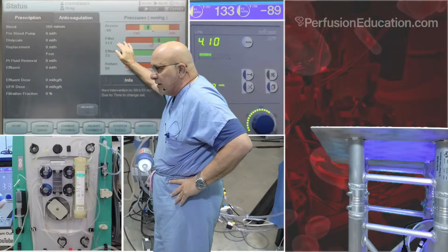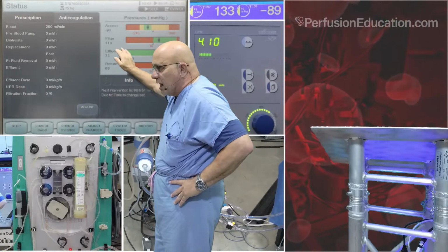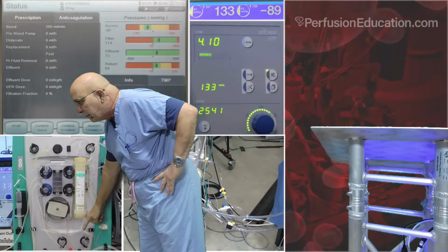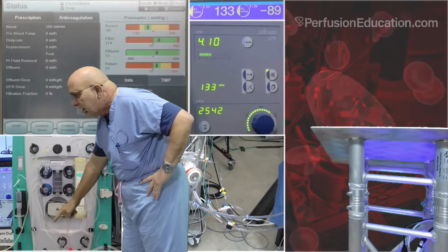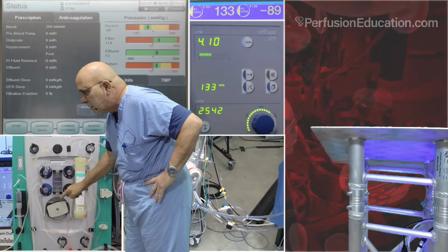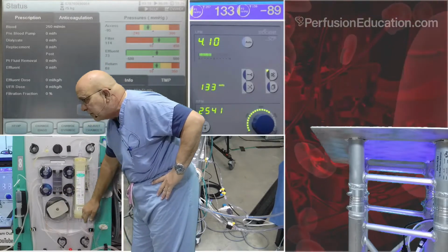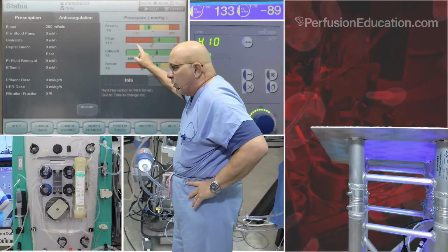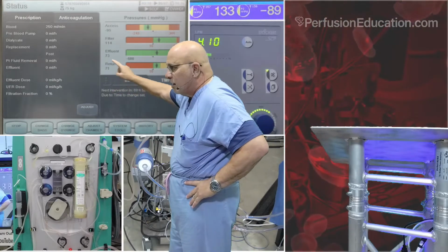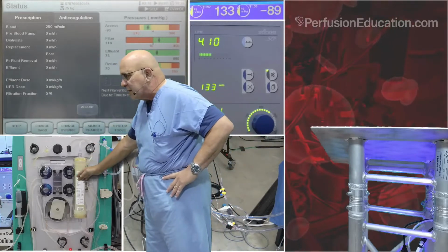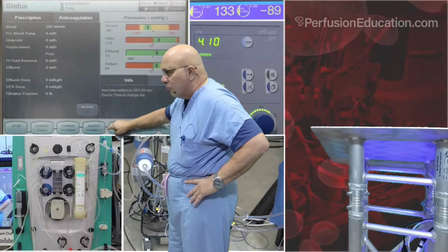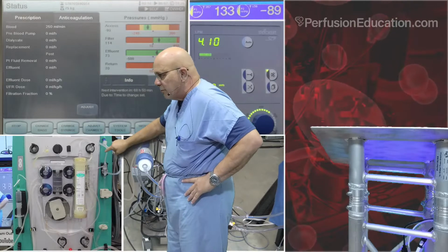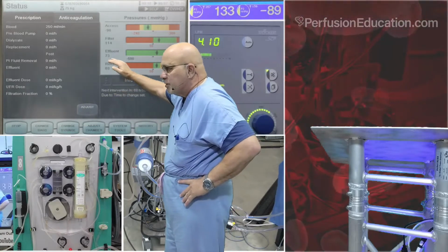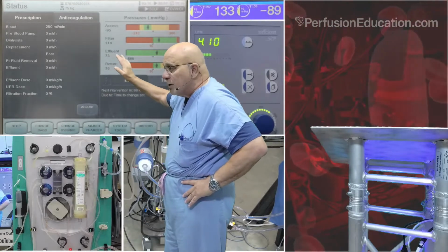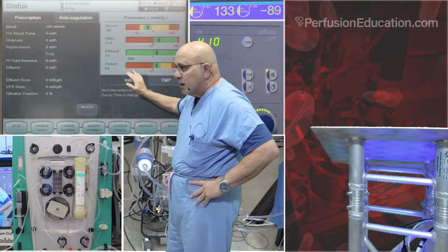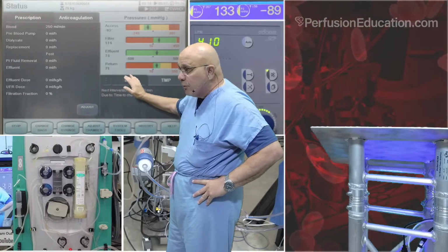You see our access is negative 94, negative 88 in that range. Our filter pressure is 114. That's the pressure that's being measured coming up this line right here. So this is your access. This is the roller pump turning this direction, clockwise, going down, coming around, you can't see it, and this filter pressure is being measured by that pressure pod, and that's 114. Your return pressure, which is here, you notice it's lower than your filter pressure because, again, there's resistance in this filter, and that's reading a 61. That's being measured right here. So this is a deaeration chamber, and that's your pressure there. And you notice our effluent pressure is very nice at a positive 73. This is what you really would love to see on any of your CRRT treatments. It makes life very, very easy when it operates like this.